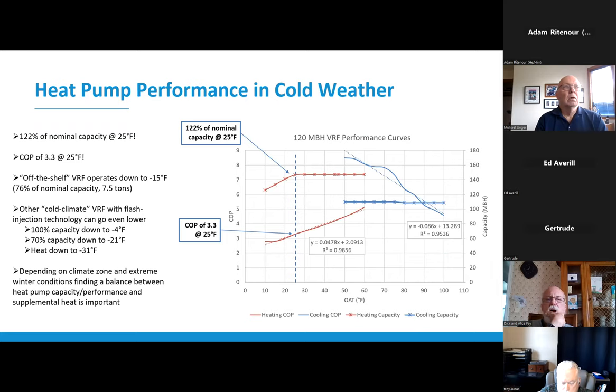So I don't know about you, but we hear this all the time that heat pumps don't work in cold climates. But modern heat pumps do actually, or VRF systems. So this is the heat pump performance curve for what we have installed in our office. And a few things to highlight here is that at 25 degrees, this unit is still capable of delivering 122% of nominal capacity with a COP of 3.3. So that's still pretty impressive at 25 degrees. And these off-the-shelf VRF systems can operate down to negative 15 degrees.